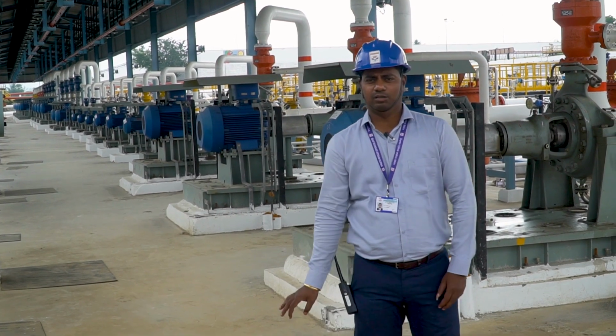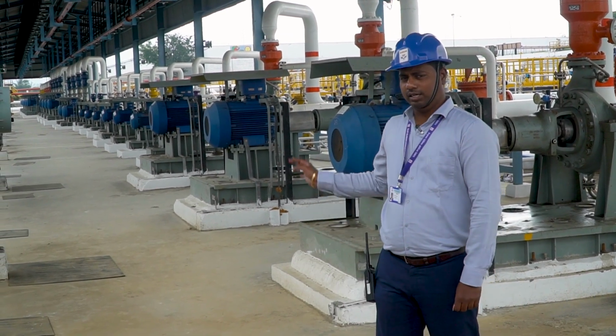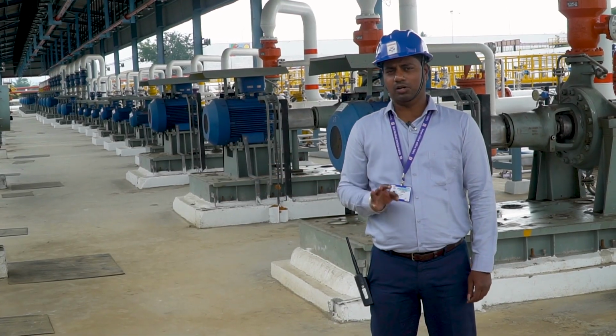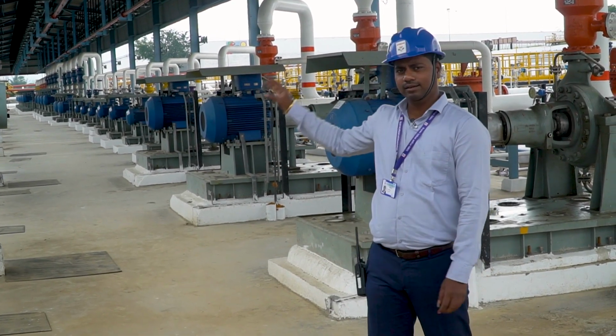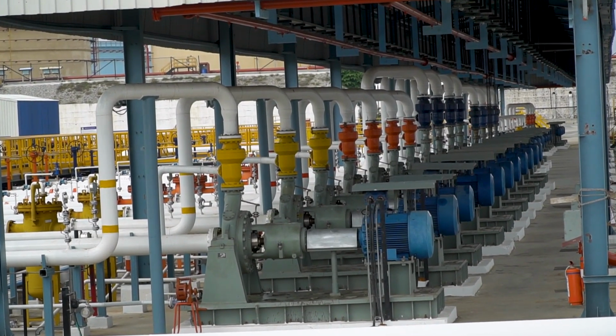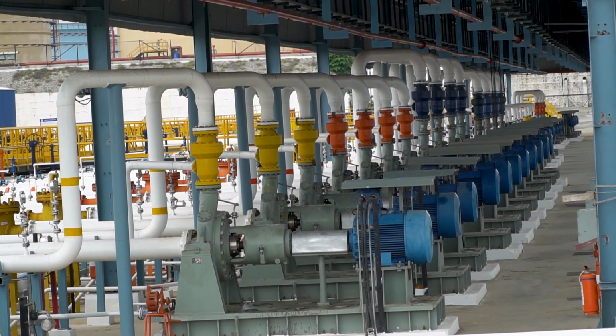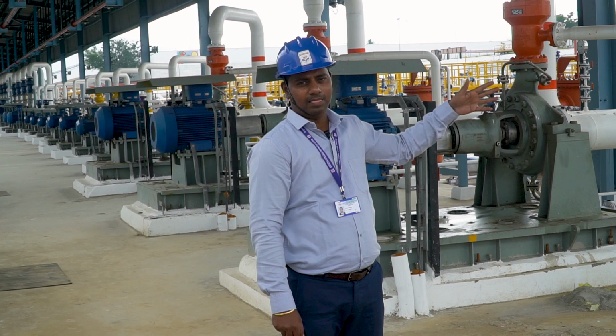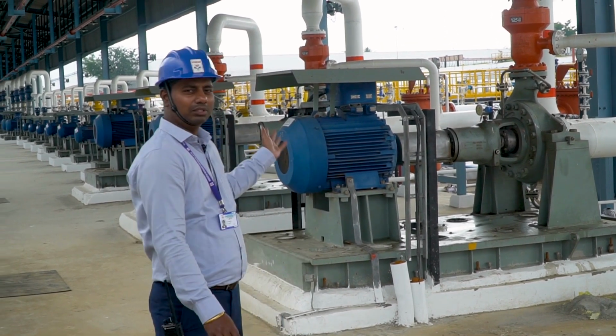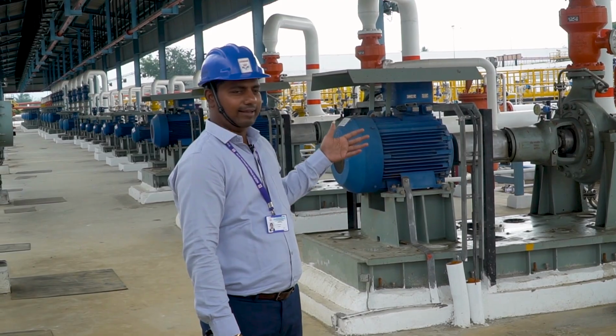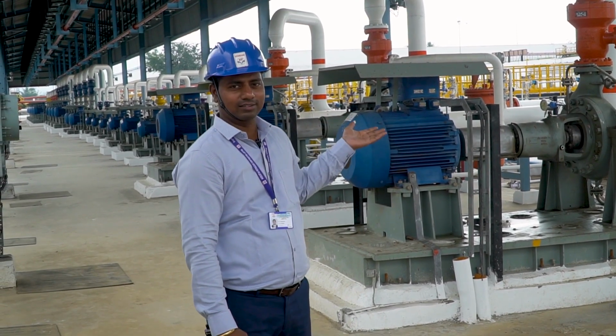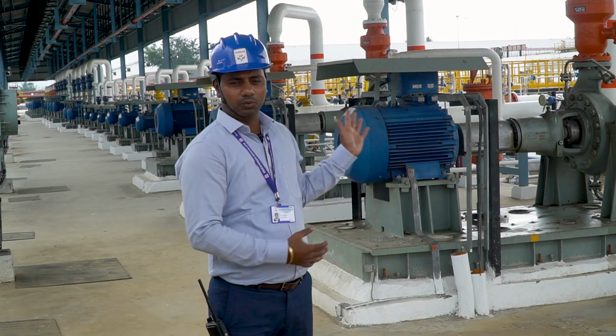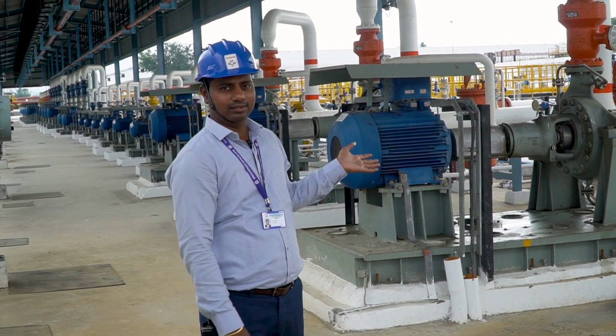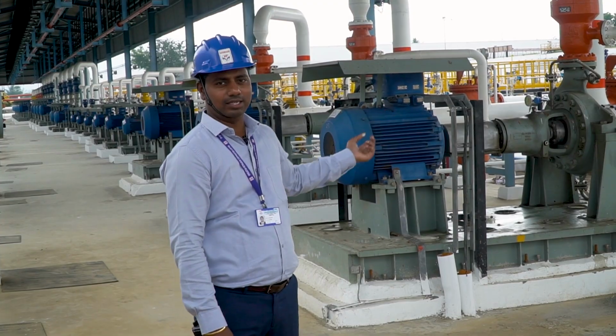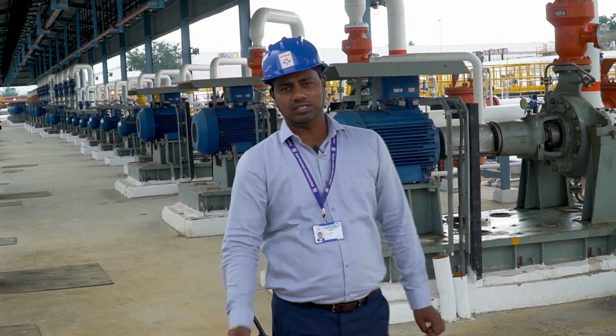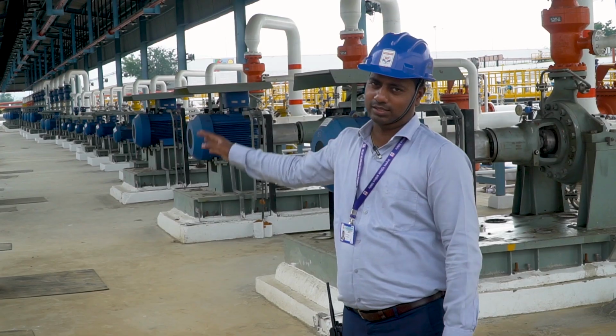So presently we are at the pump house where the TWG gantry loading pumps and TT gantry loading pumps are both in the same gantry. And here you can see the color coding. This is the MS pump which caters to the TT gantry, and these motors are connected to the pumps. On the electrical side, we need to maintain these motors. We check whether the output voltage and the input current level are correct, and the cables connected to the motors have to be checked frequently. Likewise, we need to check all the 28 motors.